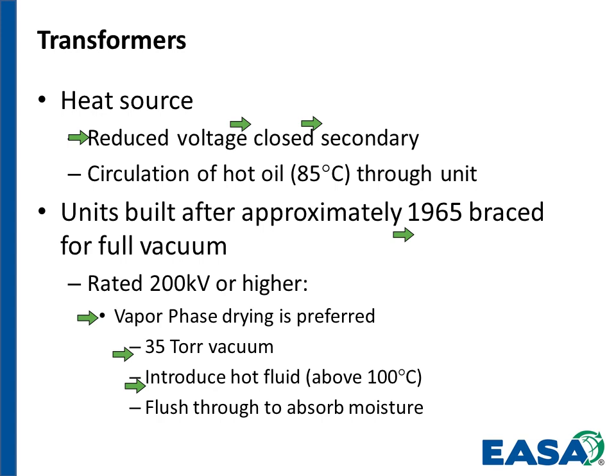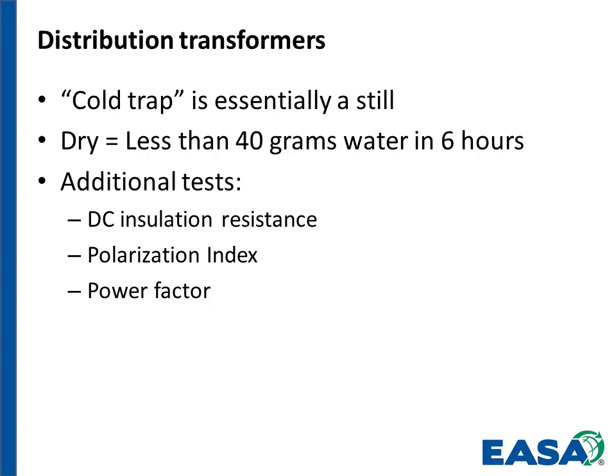So what about distribution transformers? A cold trap, which is the common means of removing moisture from a large transformer, is basically a still. So if you think of that as a still, it's a way to circulate through and distill the water out and put dry air back into the transformer. Define dry, well, the industry pretty well agrees that it's less than 40 grams of water being distilled out within a 6-hour period. We can do additional tests. DC insulation test, the megohmmeter test. We can do a polarization index test. We can look at power factor and power factor tip up.